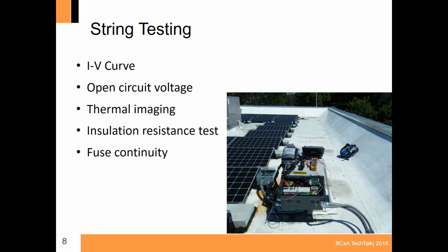Also, this insulation resistance test goes by the trade name a Megger test. Megger is one of the brands of this piece of testing equipment, but basically we're sending a high voltage through these conductors and measuring that insulation resistance just to make sure that the conductor insulation isn't damaged or hasn't been jeopardized during the installation. And we'll show you some photos of what that looks like.